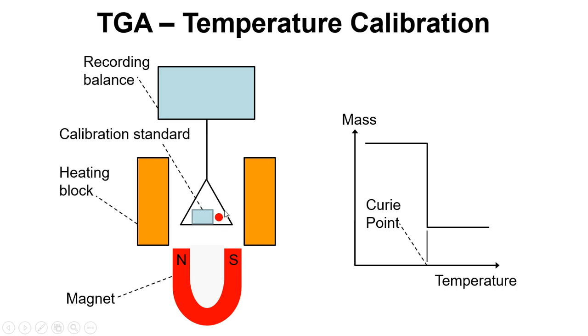This is important because our temperature sensor is next to but not actually touching the sample pan for reasons mentioned in a previous video. So it's important to calibrate this temperature reading.